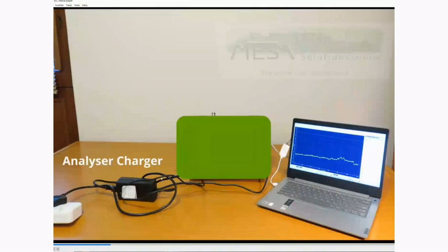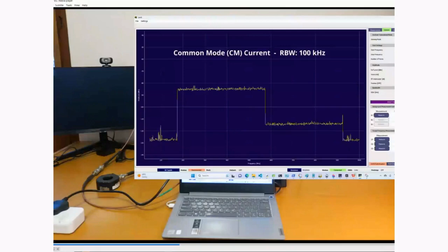So the first experiment is we take the coaxial cable to the current probe and we leave it dangling, connected to nothing on this table. And we'd like to have nothing being picked up. So we're going to start the measurement, and you're going to see the measurement appearing over here. And please notice the current probe is not connected to anything. The software is being set up to change the resolution bandwidth to 100 kHz. And here we see something coming from the current probe, recorded in maximum hold, which should pick up nothing because there's nothing going through it.